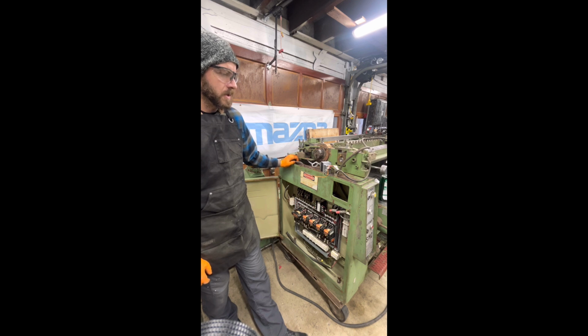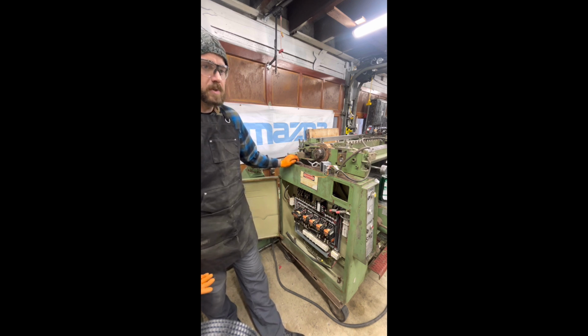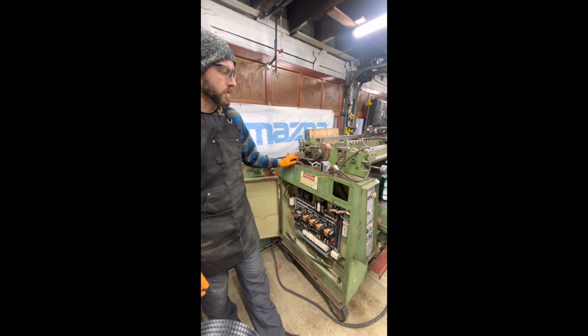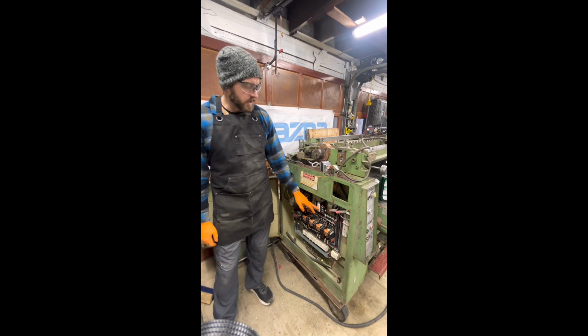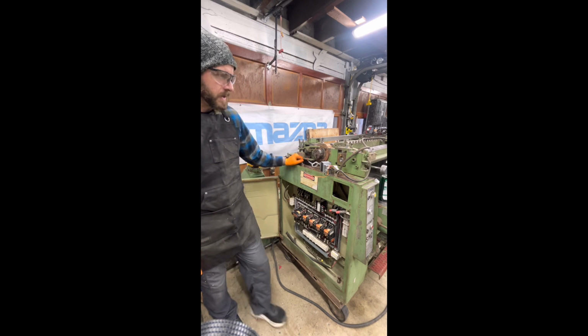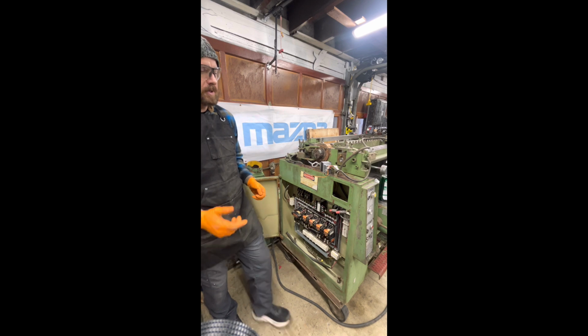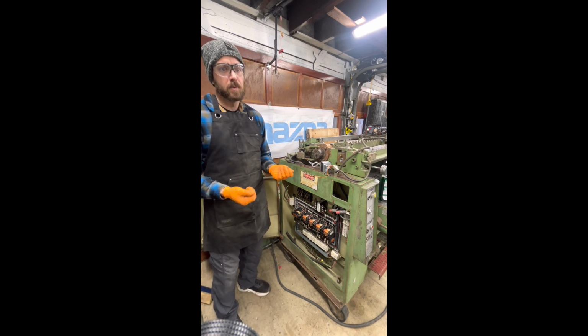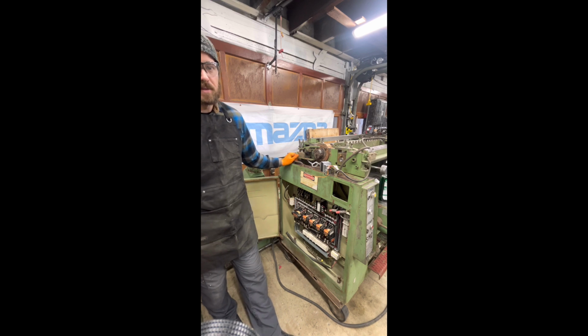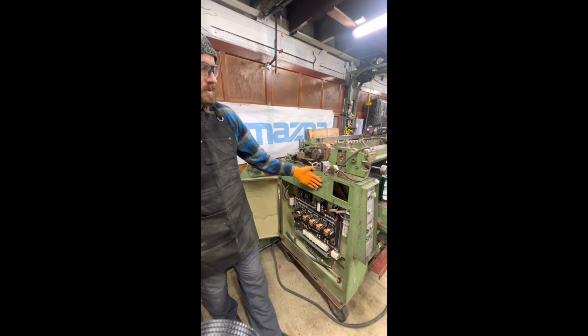And typically in those kind of applications, you would either use a 24 volt control system or 120 volt isolated control system. This is an isolation transformer, which basically is similar to how DC voltage works, where you need to be holding the positive and the negative, neutral, and the hot wire to be able to get shocked. So they use that back in the olden days for repairing old school TVs with tubes where the chassis were hot and things along those lines, and eventually worked its way into control circuitry like this. It protects you because the chassis is grounded.